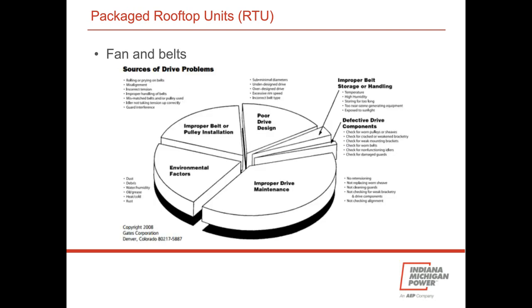When you're looking at fans and belts, this is a pie chart showing sources of drive problems. This was collected by Gates Corporation, who provides pulleys and sheaves and belts, etc. And note that improper drive maintenance, no retensioning, not replacing a worn sheave, not cleaning the guards, not checking alignment, is really a third of sources of fan drive problems. The rest being environmental factors or improper belt or pulley installation, etc. So maintenance has a big impact on that.